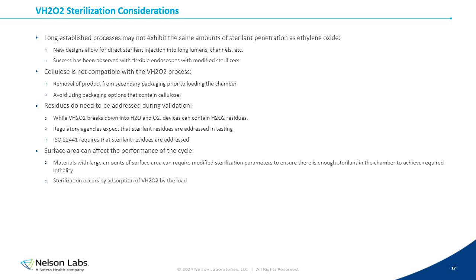One thing I just want to mention in closing is that residues do need to be addressed during validation. We have seen in the past where some claims have been made that we don't need to worry about residues because everything breaks down to water and oxygen. However, regulatory agencies expect that we will examine sterilant residues. It is addressed in ISO 22441. And so it's something that we need to make sure that we're looking at during validation.